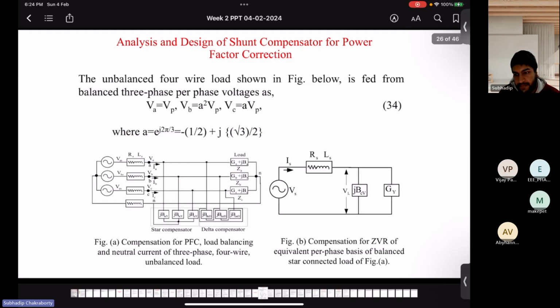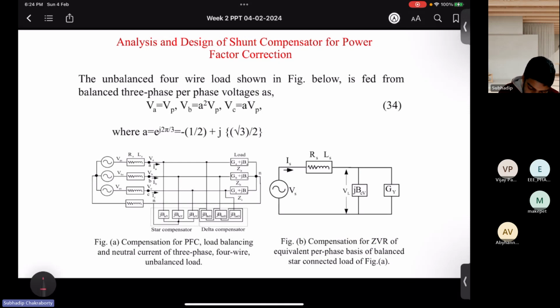Power factor improvement, as compared to the 3-phase 3-wire system, all features we need to provide. In addition, also we need to provide the zero sequence and neutral current compensation. Because writing neutral current compensation inherently means zero sequence compensation, because you know in power systems we had learned these 3 times of the neutral. So once you break down, you will see both are complementing each other. So either you say zero sequence compensation or neutral current compensation. So this additional feature we need to provide.